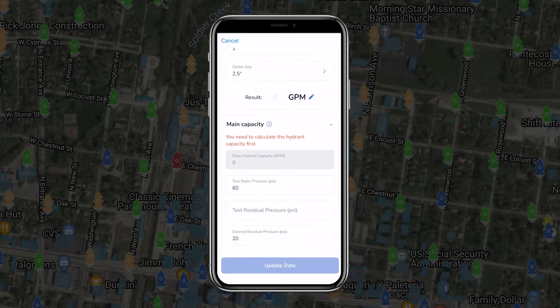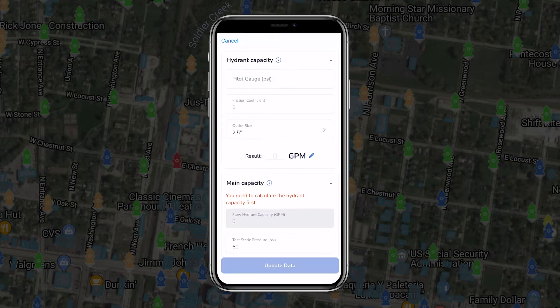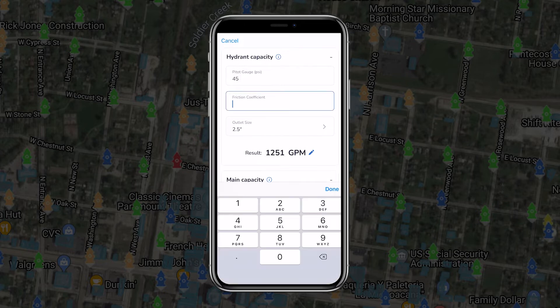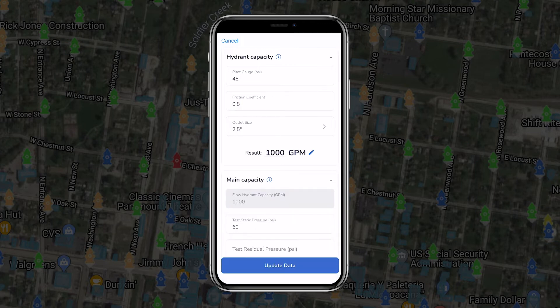Once the static pressure reading has been recorded, another team member at the flow hydrant will measure and record the friction coefficient and outlet size of the flow hydrant and attach a pitot gauge for measuring pressure.